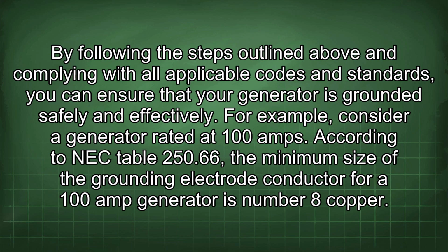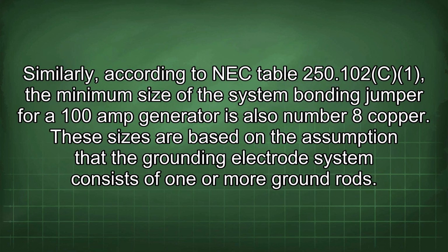For example, consider a generator rated at 100 amps. According to NEC Table 250.66, the minimum size of the grounding electrode conductor for a 100 amp generator is number 8 copper. Similarly, according to NEC Table 250.102, the minimum size of the system bonding jumper for a 100 amp generator is also number 8 copper.